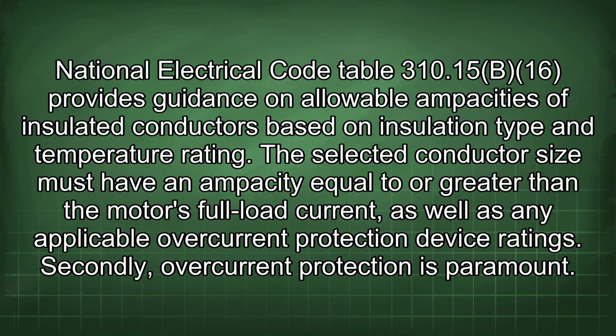National Electrical Code Table 310.15(B)(16) provides guidance on allowable ampacities of insulated conductors based on insulation type and temperature rating. The selected conductor size must have an ampacity equal to or greater than the motor's full load current, as well as any applicable overcurrent protection device ratings.